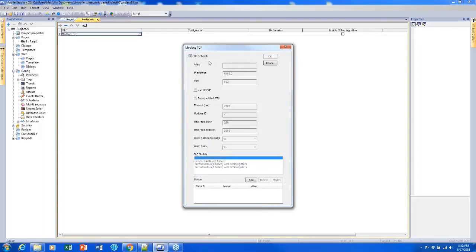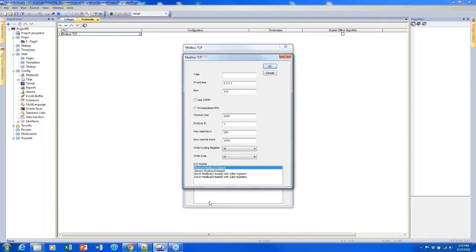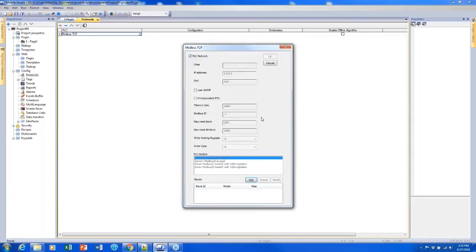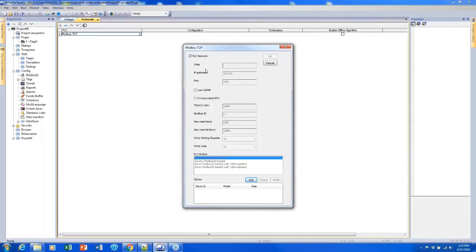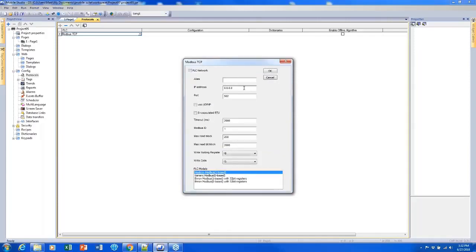And what this will allow us to do is add multiple PLCs that we're going to connect to at the same time that use the same tag database. So I could simply click add here and begin adding them. The number of PLC slaves that we support here varies depending on the protocol, but usually it's a pretty large number. I'm just going to uncheck that and only have it set up for one PLC.